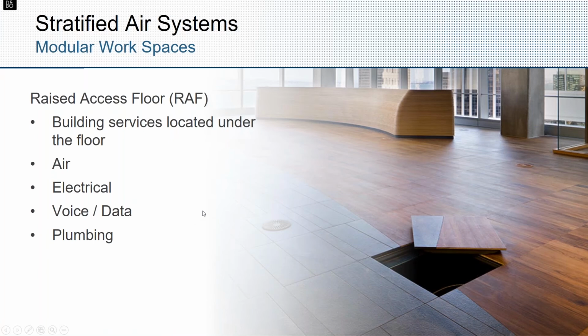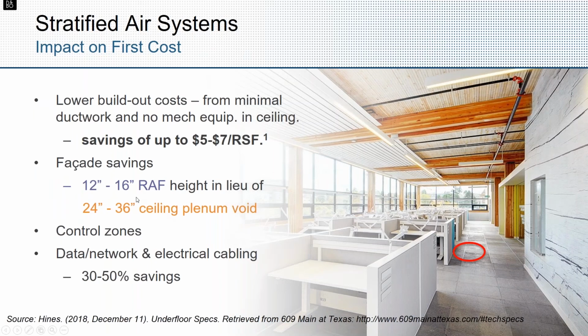An owner would go with a raised access floor for putting power and data underneath the floor, increasing the floor height a couple inches up to 12 inches. We used to see 16 inches, now we're seeing it lower, 10 to 12 inches, really optimizing the amount of interstitial space down to that level. You could see a lot of facade savings. A lot of times you might just keep that additional space occupied and have higher ceiling heights, but for a mid to high rise, you could see significant facade savings with an exposed ceiling.